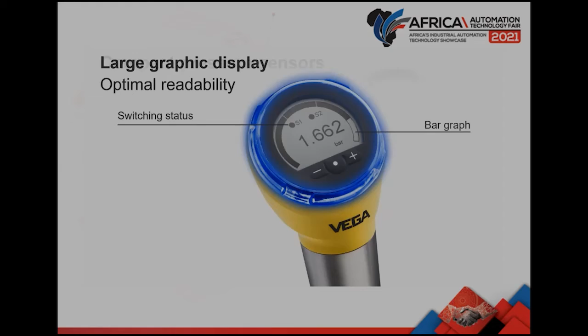On board the pressure transmitters, as I mentioned, there's a large LED ring. With the pressure switch functionality, these devices have the 4 to 20 output as well as transistor switching capabilities, where it can be configured purely as a pressure switch or a transmitter and a switch both in one. This LED ring shows you the switch status depending on the configuration and at which pressure points the switching should take place. And there's a numerous array of colors that can be selected on these devices.